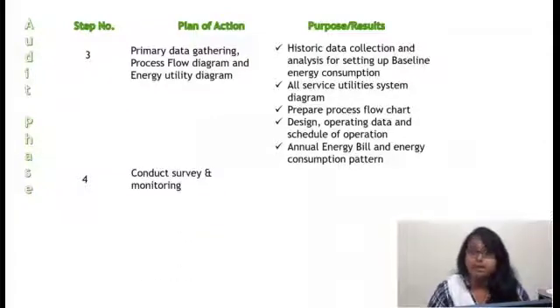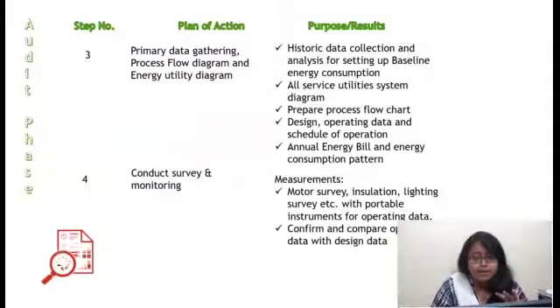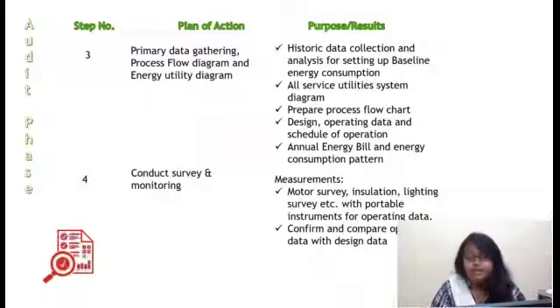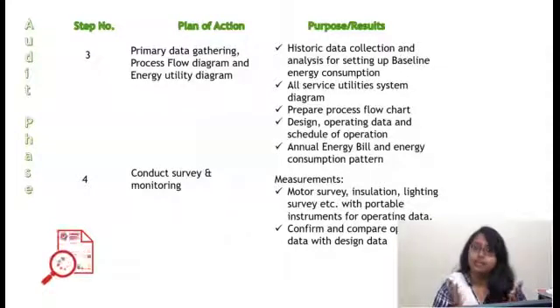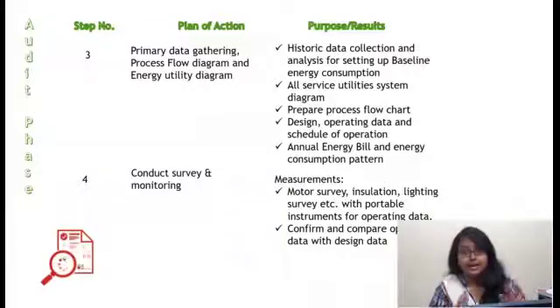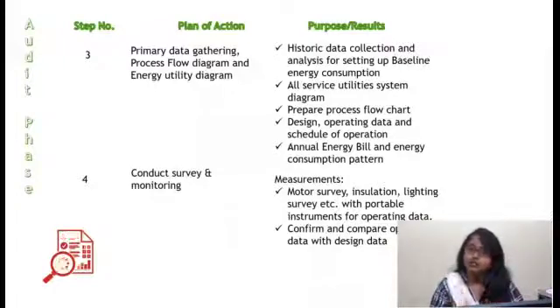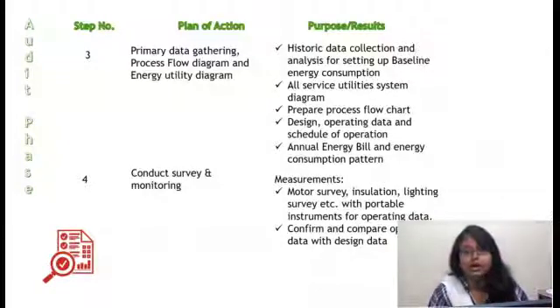Next is step 4: conduct survey and monitoring. It is also important to cover different zones of your industry. So you need to perform different measurements such as motor survey, insulation survey, and lighting survey. For this, obviously many instruments need to be utilized for operation data. You can confirm and compare this operating data with design data — that is, the manufacturer promised a certain efficiency, but is your system working with that efficiency and delivering that level of energy conservation?